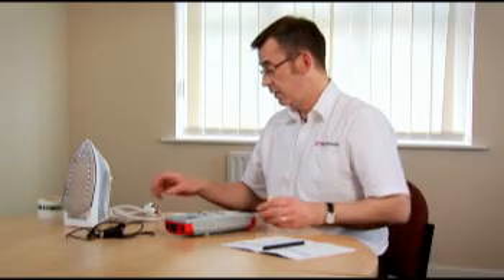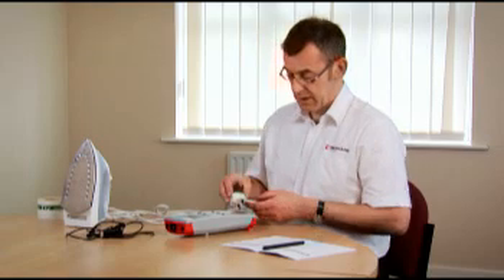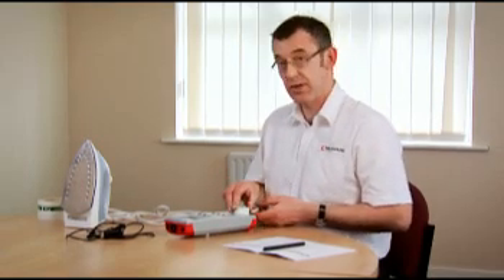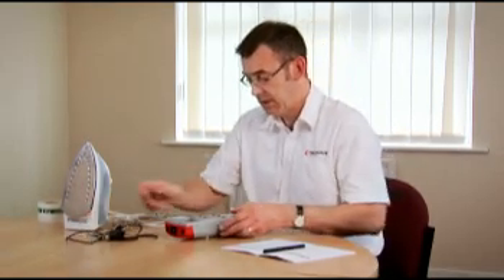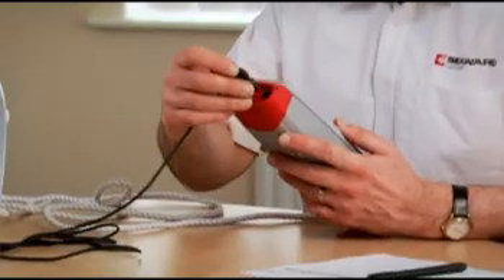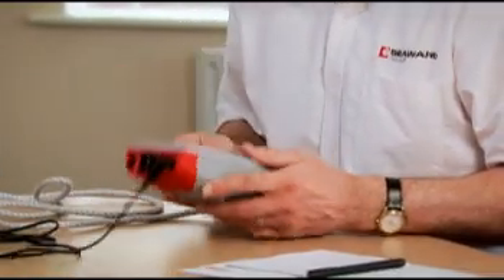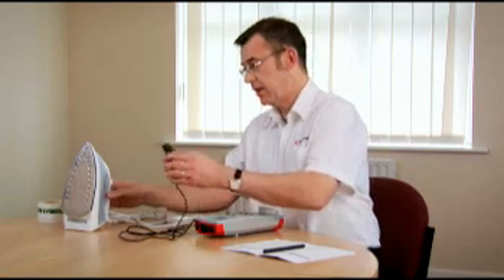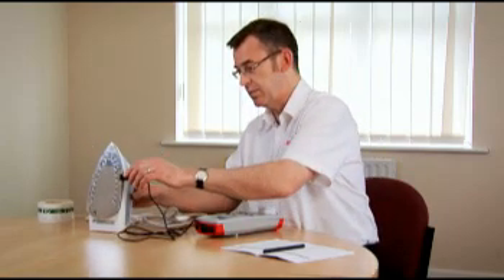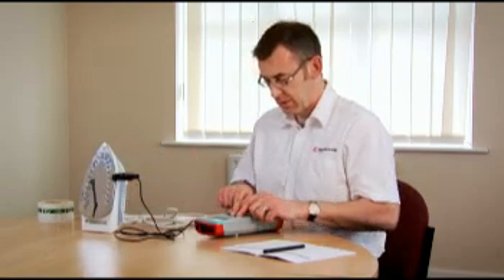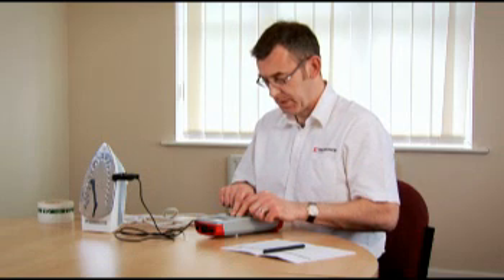To perform the Class 1 appliance test, first of all, we connect the appliance to the test socket on the front. We connect up the earth continuity test lead to the socket on the end and connect up the test clip onto the exposed metal.